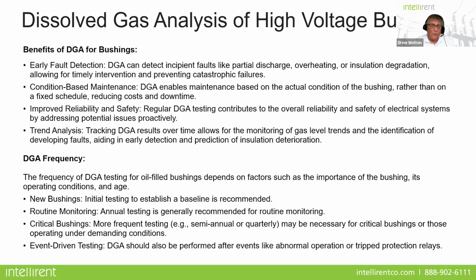Well, when do you do DGA? First and foremost, you should do it on new bushings so you can get a baseline. It's always recommended. Routine monitoring: annual testing is recommended. You should shorten that period on critical bushings.